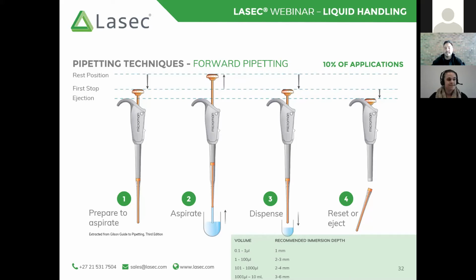You would then insert that tip into your solution, again keeping in mind your immersion depth. You don't want excessive amounts of liquid on the outside of that tip. Once you are happy that it is submerged sufficiently, you can release that push button back to its rest position. The plunger will move up and it will physically pull in that liquid. Much the same as dispensing with an air displacement pipette, you will then again depress that plunger until the liquid is forced out of that tip.